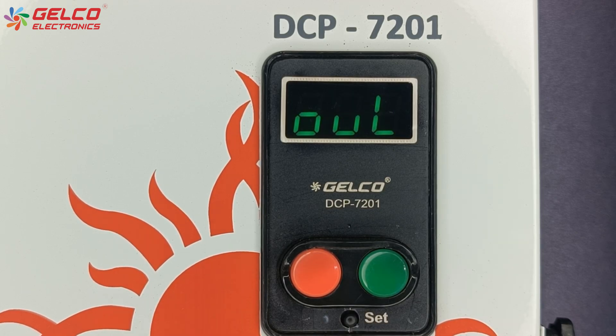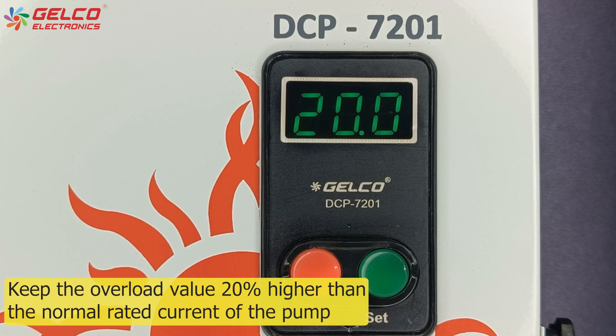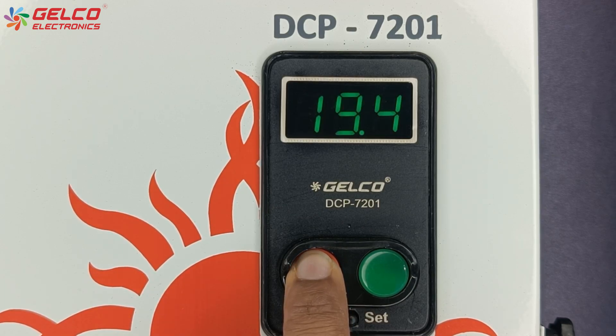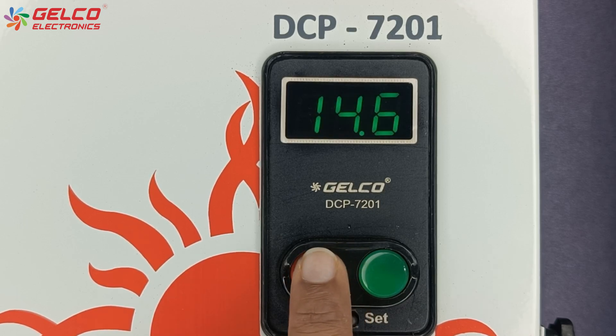The overload option will appear on the display. You have to set the overload protection value 20% higher than the normal rated current of the pump. Here the normal rated current of our pump is 12.1 ampere, so its 20% will be 2.4 ampere. So we will set the overload value to 14.5 ampere. Press the set button after the value is selected.